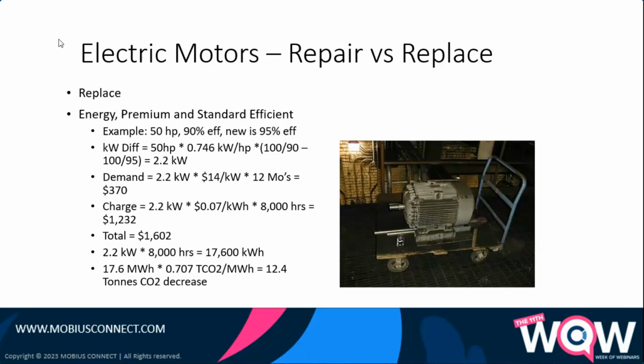I would look at that and say, okay, if we're looking at 8,000 hours, that 2.2 kilowatts times 8,000 hours is 17,600 kilowatt hours. Now, I could change that to pounds of CO2 pretty readily, but the number would be massive. So what I usually like to present is tons, because it sounds bigger for one thing, but the number looks more realistic from the standpoint of when you're looking.